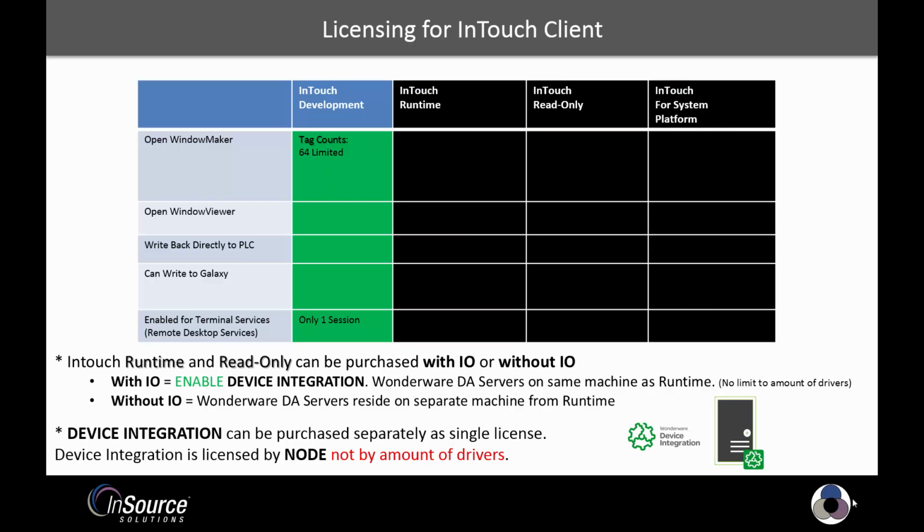As we remember in the previous video, device integration is licensed by node, not by the amount of drivers. Now there is an InTouch development tag with a 64 tag count. We call that the limited. This is the only development license that can be used as both development and a legitimate runtime license. All of the other development licenses are meant to be used for testing purposes when switching between Window Maker and Window Viewer. However, this InTouch 64 tag limited development license can be used for both.